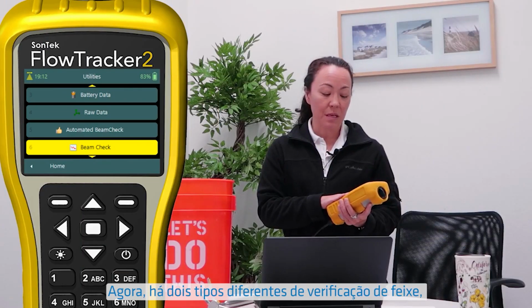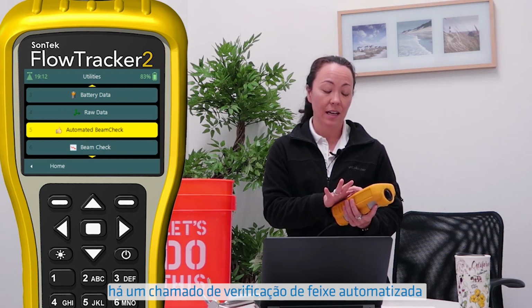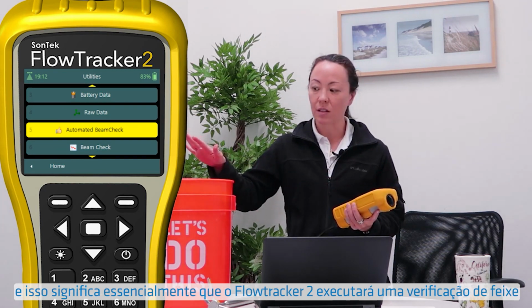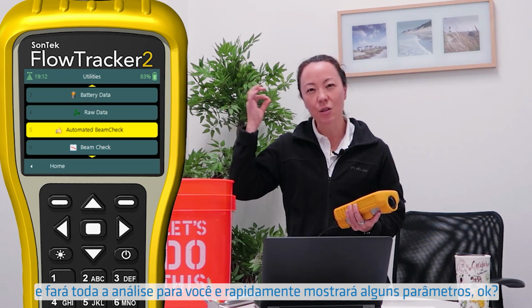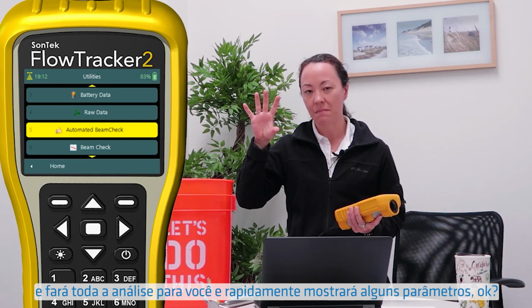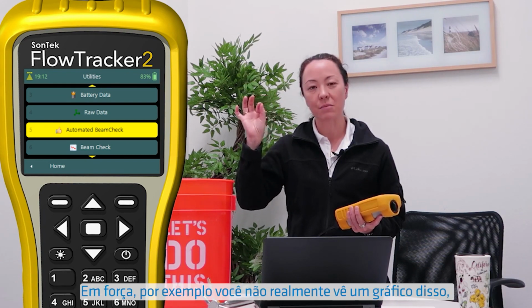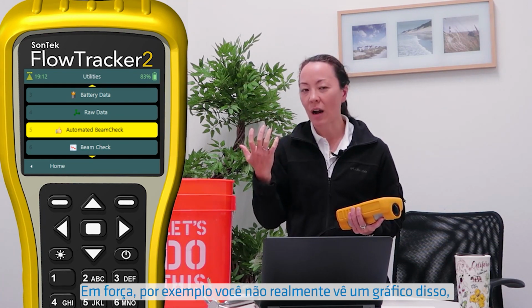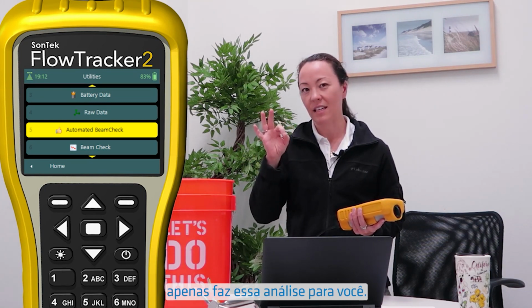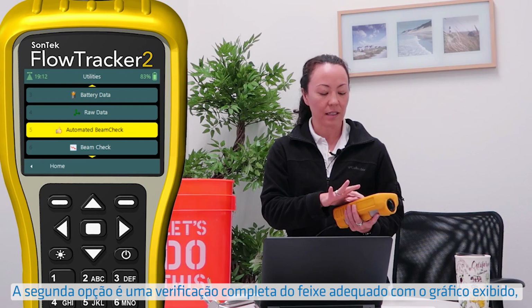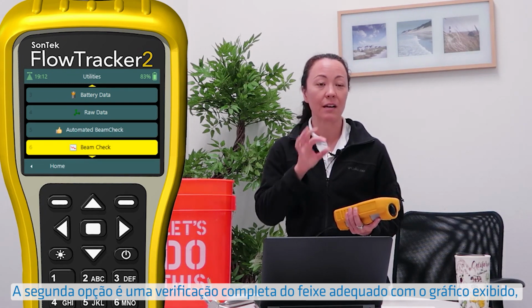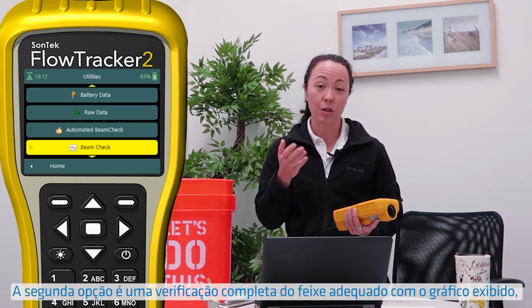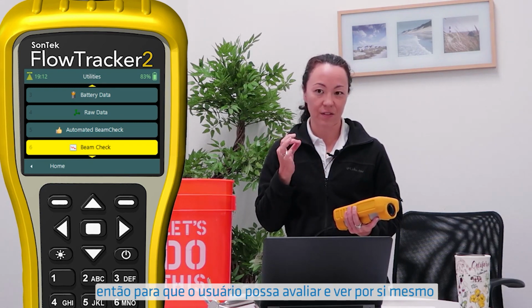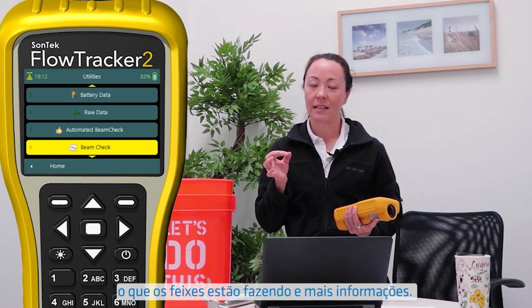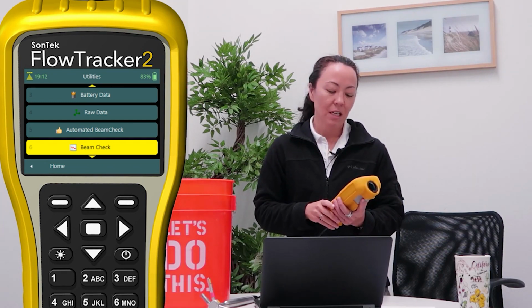And then we move down to our beam checks. Now, there's 2 different kinds of beam checks. There's one called the automated beam check, and that essentially means the FlowTracker will perform a beam check and do all the analysis for you and quickly spit out some parameters on beam strength, for example. And you don't really see a graph of it. It just does that analysis for you. The second option is a full proper beam check with the graph displayed. So you, the user, can assess and see for yourself what the beams are doing, and it's just more information. So let's go through both of them.